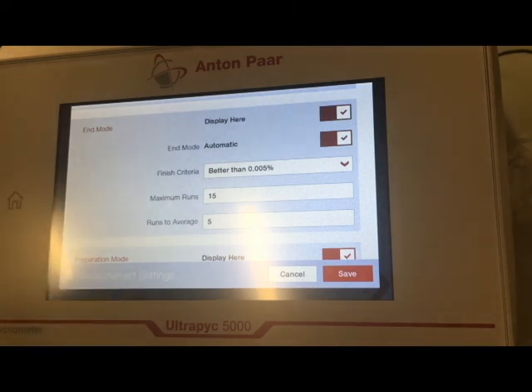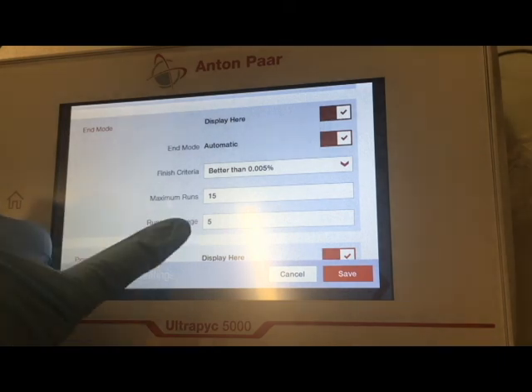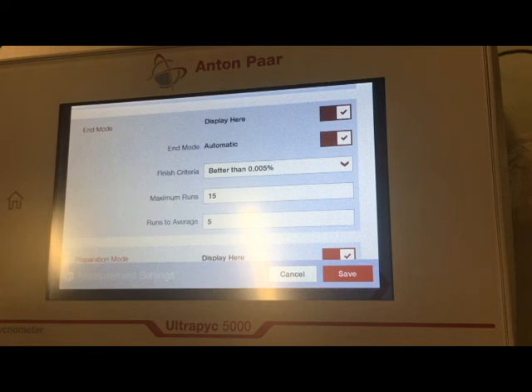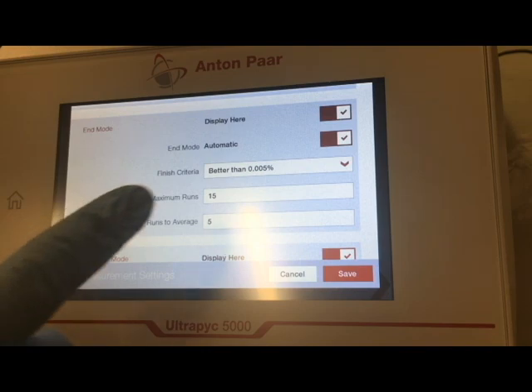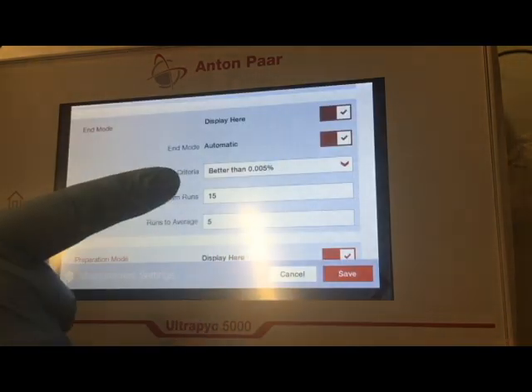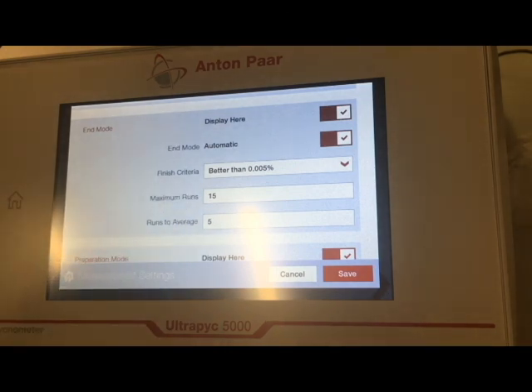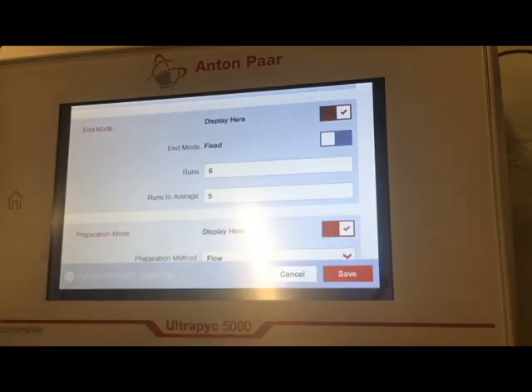What's going to happen here is it's going to run 5 sequential runs, and it's going to average those 5 together. If the error within those is 0.005% or smaller, it will stop the scan there. That would be a very fast and a very reliable scan. However, if after the 5th one it does not have this low error percentage that we've selected, it's going to run a 6th, and then it will average runs 2 through 6 to try to get this error percentage. It's going to do that all the way up to a maximum of 15 runs. If it hits 15 runs, whether or not it's hit that 0.005%, it's going to stop your scan. You can change those as you need, but 15 and 5 are the traditional or the normal. If you choose to do fixed, you choose the number of runs and the number it will average, and you will have to calculate your own error percentages if that's something that matters to you.